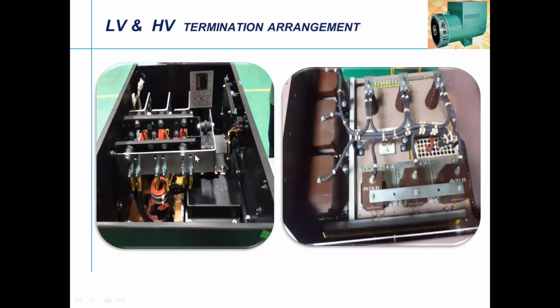So this is the LV generator terminal box, and this is the HV generator. Again, in the LV generator, as we were discussing, some protection is required on the current and QDC, which has been built in, where the customer can connect the outgoing cables. This is the neutral, RYB, and this is the neutral where the customer can connect. If it is a vertical one, the customer can even go for sandwiched bus bar connections where the terminals can be connected. This can be LHS or RHS, whatever the customer requires. Before that, we have to inform the manufacturer who is going to select the generator. The same as the HV generator, where you have the PTs and CTs fitted across and the output cables taken out. This is a three-phase star connection, and the neutral is taken from here, and the phases RYB for the 11 kV output are taken from this.